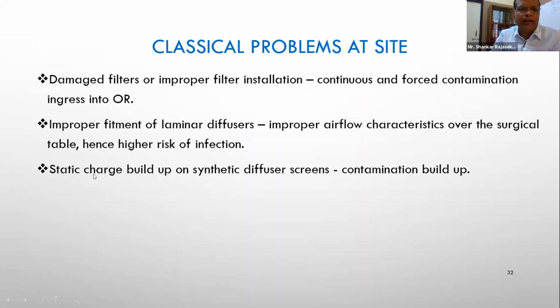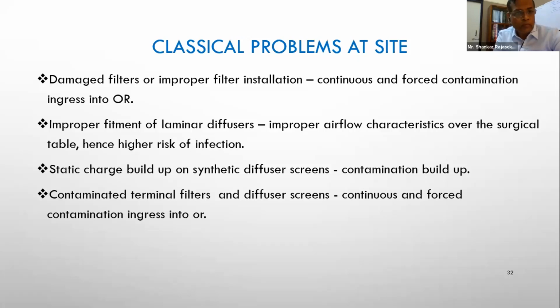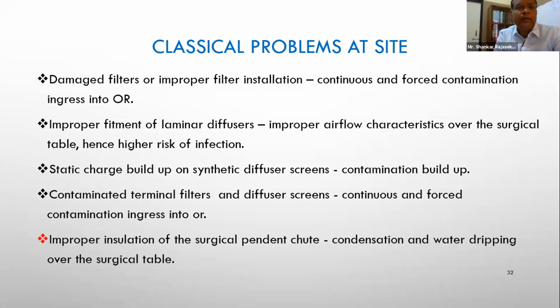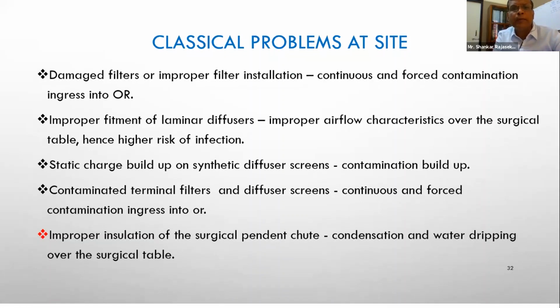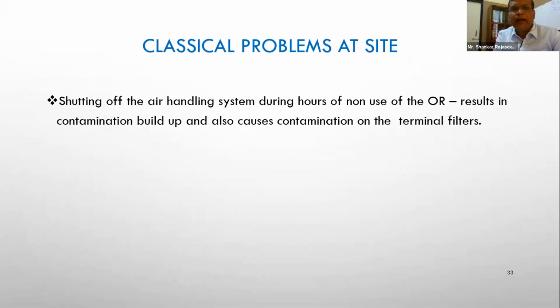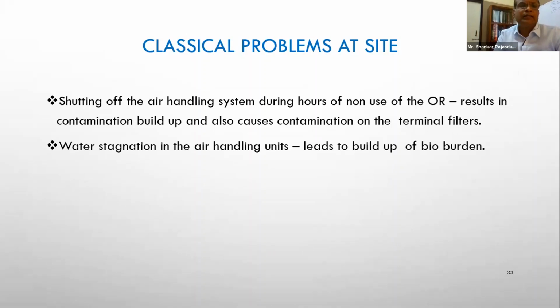Static charge: using the wrong kind of material leads to static charge build-up on the synthetic diffuser screen, and that makes it possible for contaminants to be attracted and built up there. In many places we have seen contaminated terminal filters and improper insulation of the surgical pendant chute, which leads to water dripping on the surgical table. Shutting off the air handling system during the non-use hours of the OR is a common problem that we face, but that results in contamination buildup, and this is one of the reasons why the terminal filters get contaminated.